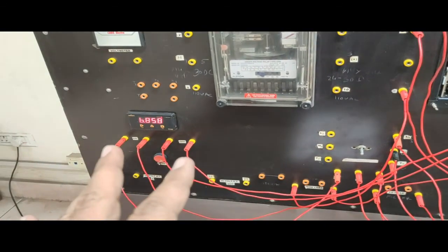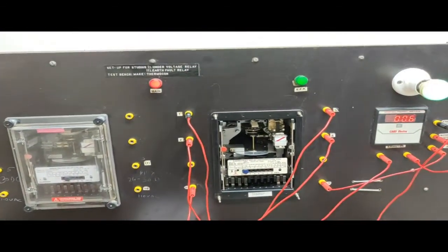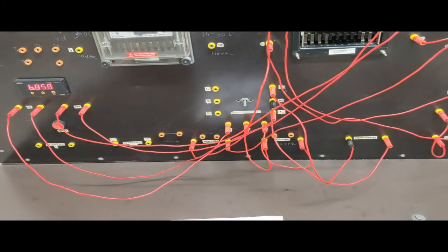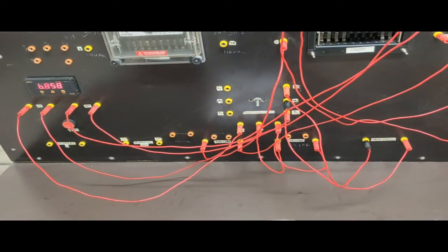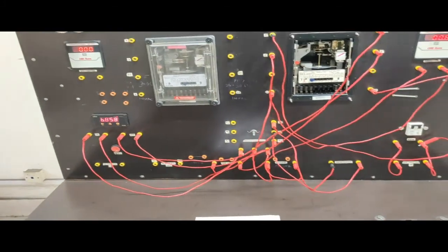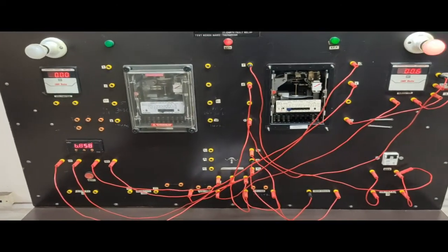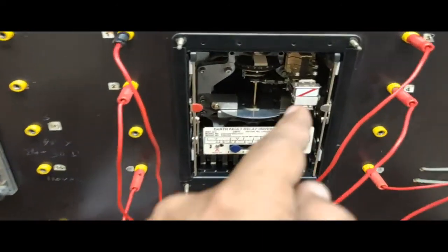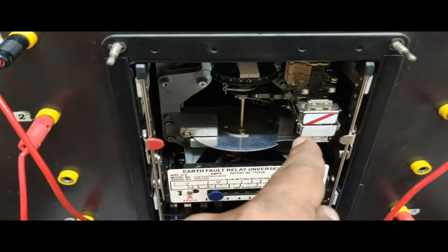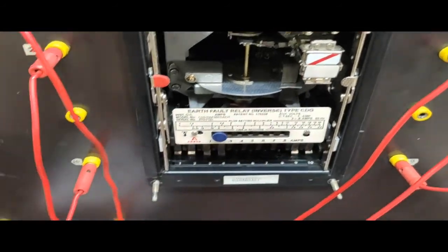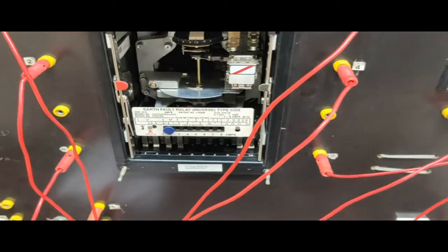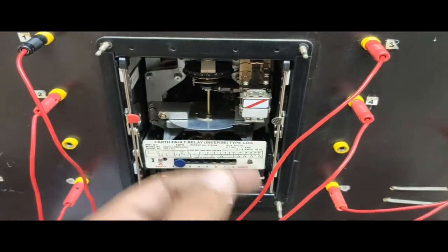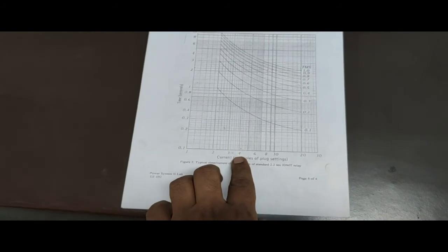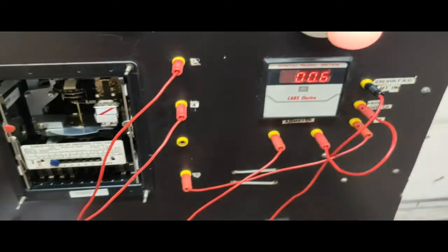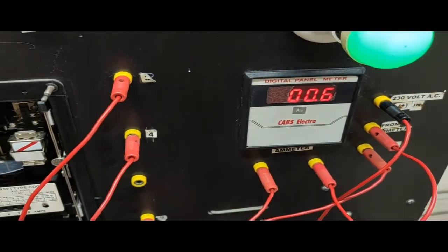That is the actual time taken by the relay to generate the trip signal, and theoretically it should be around 6.2. So now you need to find out how much error there is, or whether there is any offset or not. And after every operation you see the flag which goes down. This is the relay flag and it goes down. After every operation you need to manually pull it up. Now come to another thing. If I want to make the plug setting multiplier 4, then we need to give the current as 0.8.